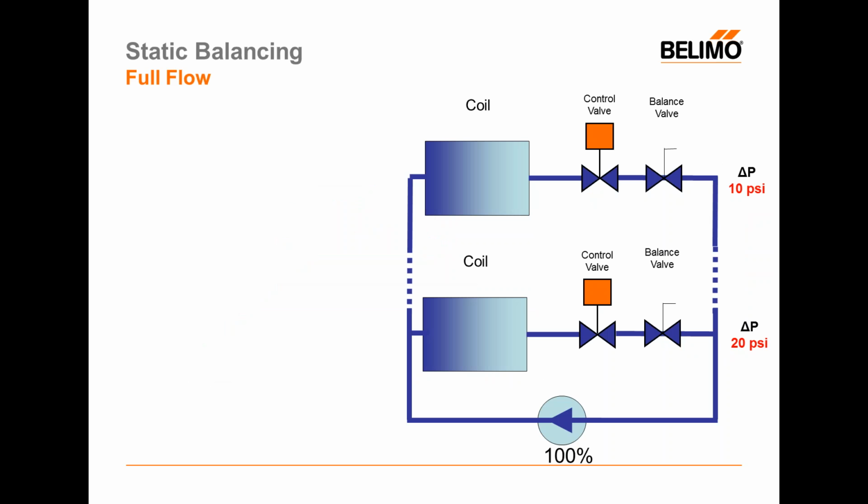Let's take a look at the idea, thirdly, of static balancing versus dynamic balancing, and this is really where a flow control technology valve versus position control is going to give you a much greater advantage. So let's take a look. On your screen, what you're going to see here is an oversimplification of a building, basically. Down at the bottom there's my pump, and that's going to be my distribution pump for my building. We'll just call this building, say, a 10-story building.